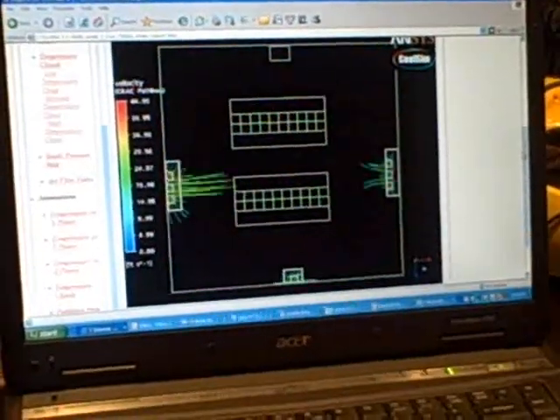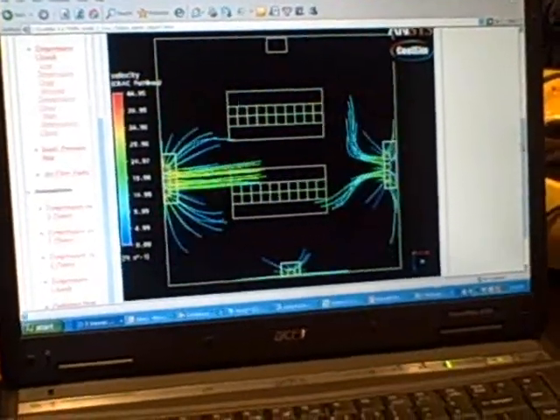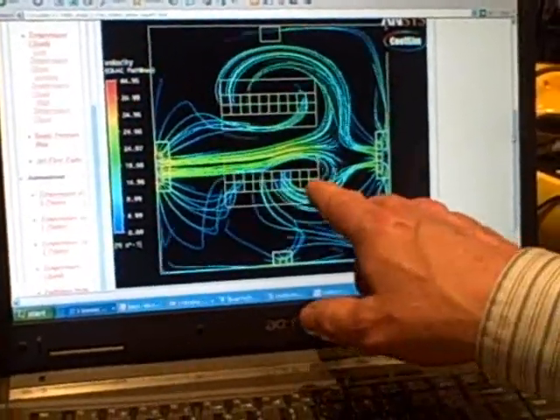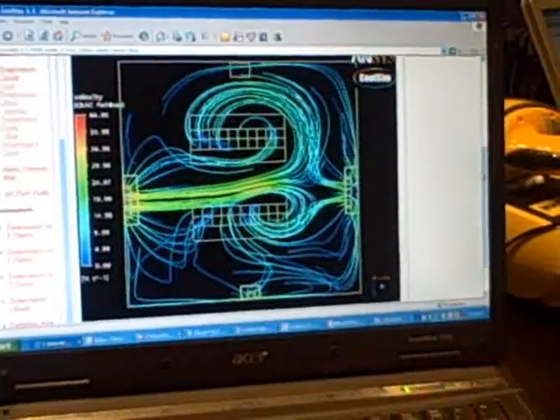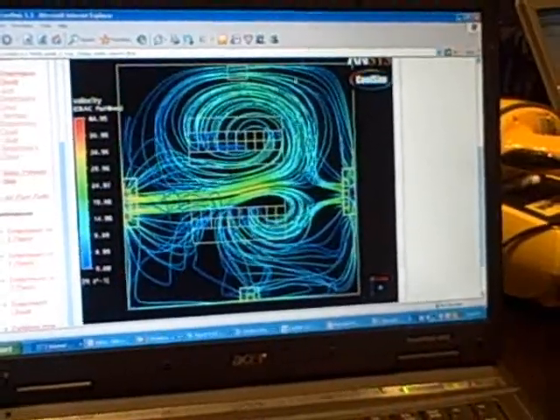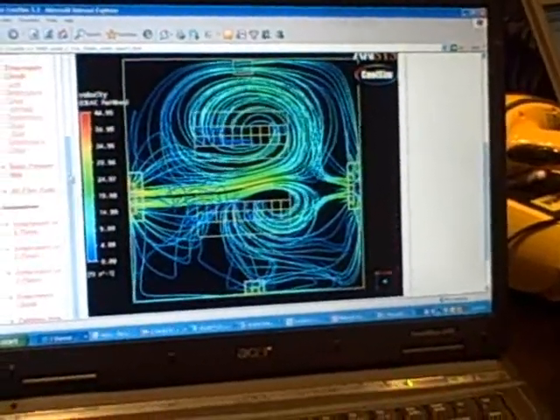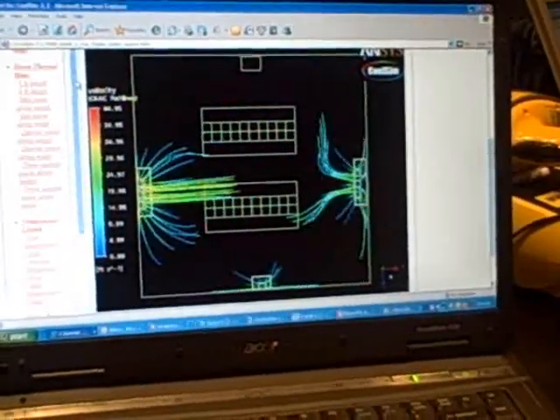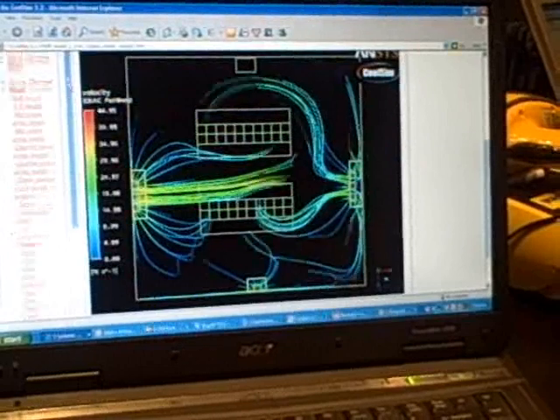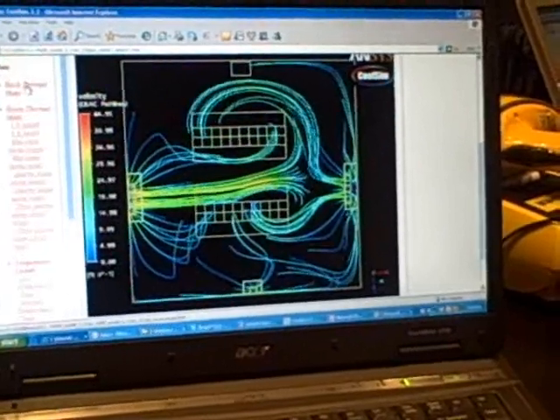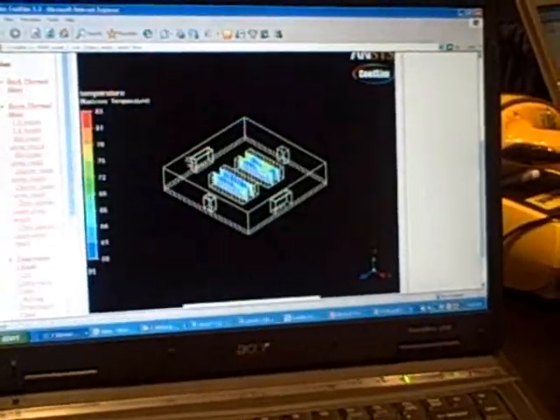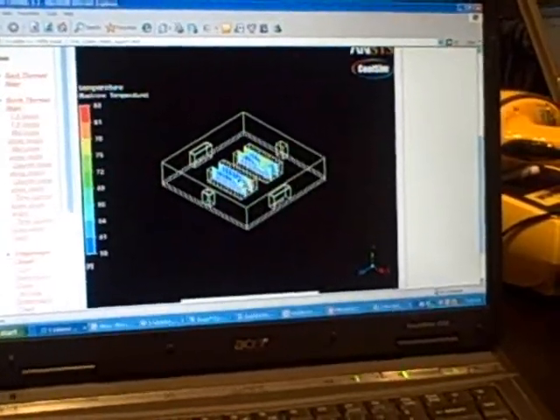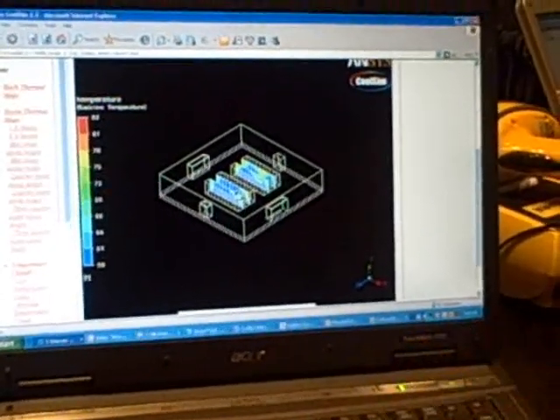As you go back to my rack inlets, you'll notice they're hot right there. Let's take a look. To scale up and take a look at our rack inlets. And you'll notice they're hot right there. It's my rack thermal maps. Look at the heat. It's correlated to the vortex.